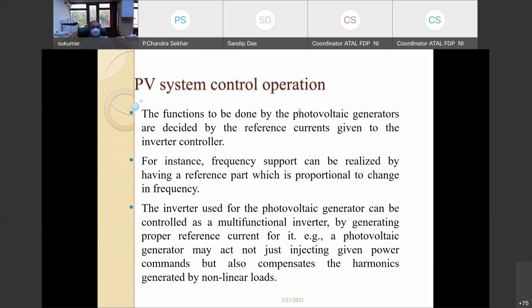Now, the PV system control operation can be extended, where frequency support can be realized by having a reference current which is proportional to the change in frequency, and that can be integrated into the photovoltaic control. Apart from frequency, many other things can also be integrated, like harmonics and voltage control, so that the grid connected inverter can act as a multifunctional inverter per se.